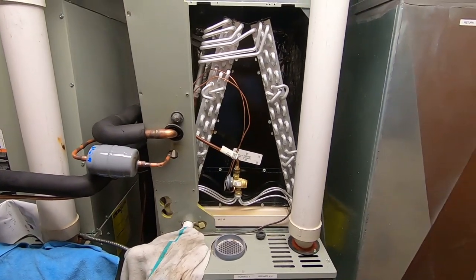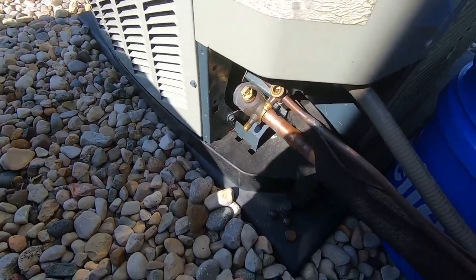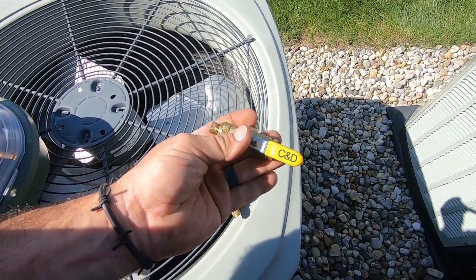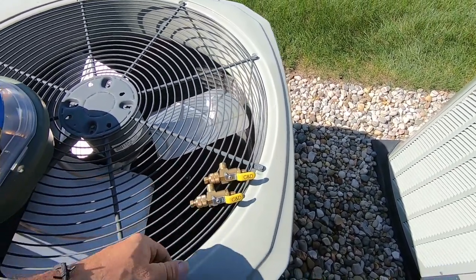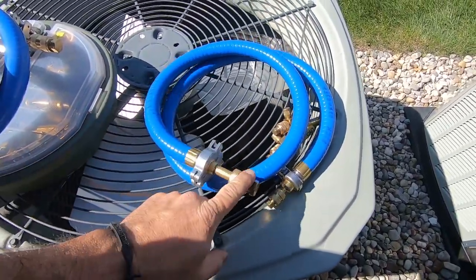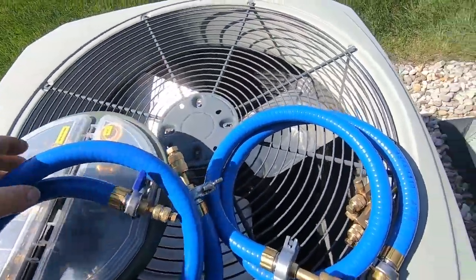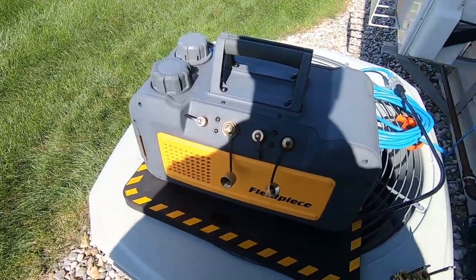So far we have the Schrader cores pulled out and our core tools ready to go. I mentioned in the past I like my C&D tools — the ones I got with my True Blue hoses are pretty nice too. I just want to wear these out first before I start into the next ones. Hoses are ready to go — I've got the half-inch fitting and the three-eighths fitting on the other end. We're going to get them hooked up to our 8 CFM Fieldpiece pump.